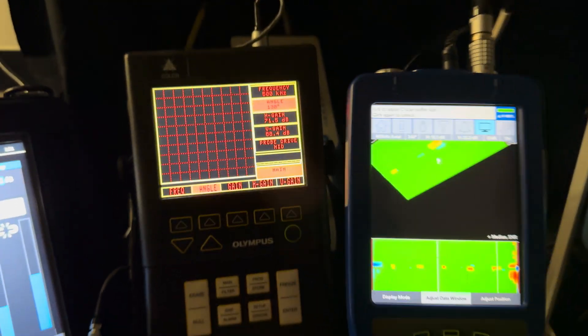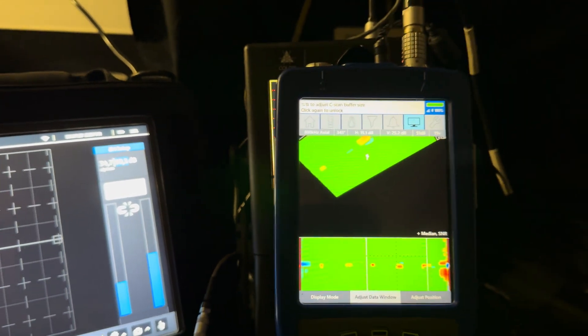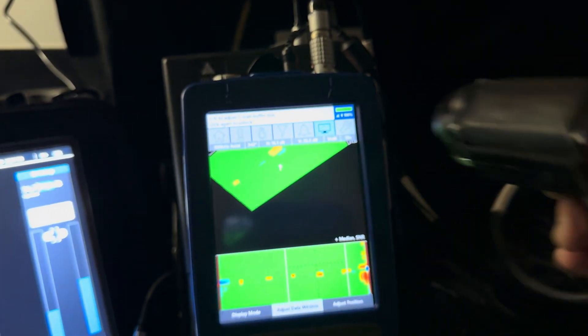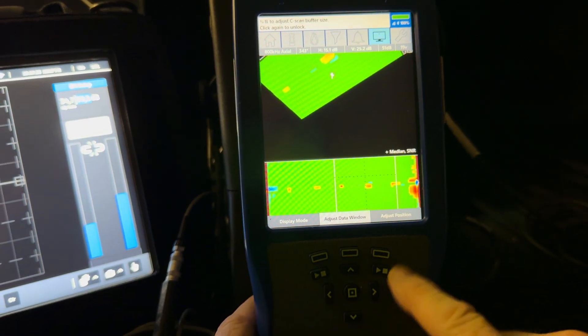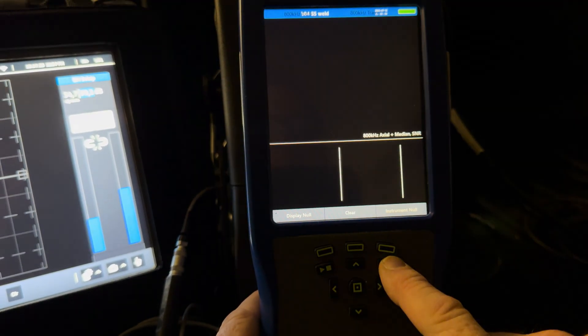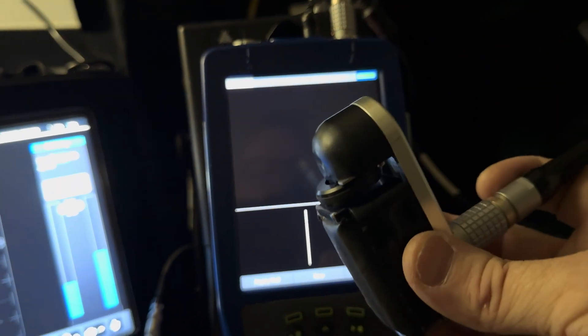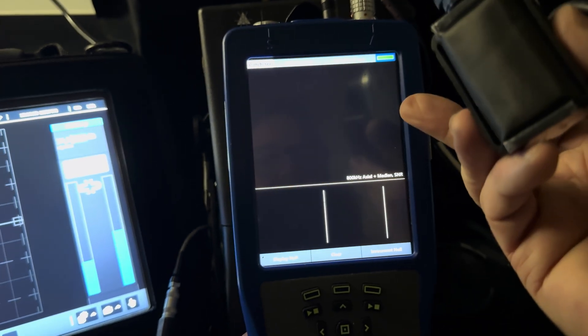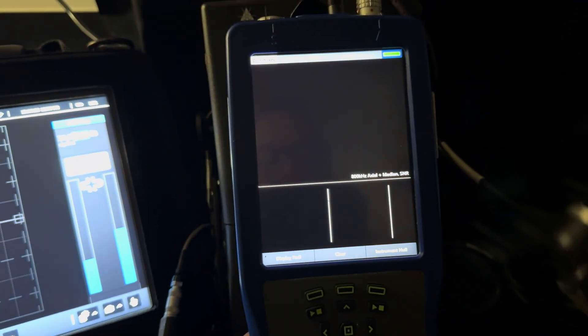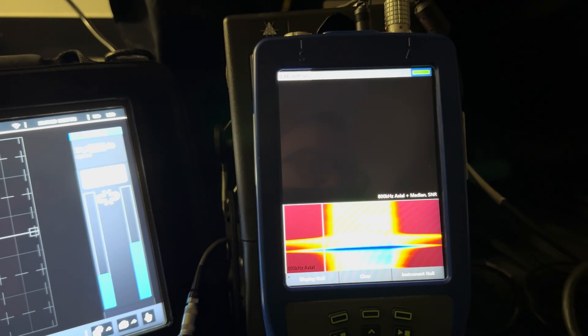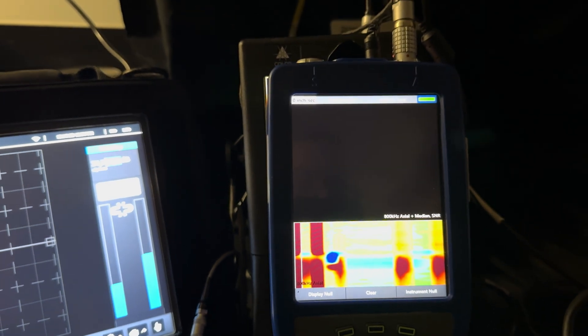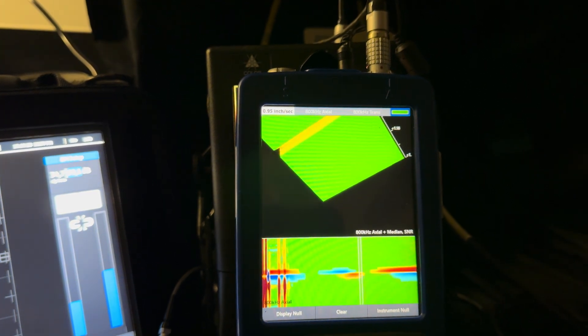Now the last tester I have to show you today, we're going to be using the MS-21C. Actually it's not the last, I still have a surprise for you. Okay, so this is a surface array probe and I'm going to just start up the tester, start the acquisition mode which is right there. And this array probe has an encoder wheel on it, so you're not going to see any data on your screen until this encoder wheel starts to move. But when I lay the array probe down onto the material and then pull the probe towards me, we're going to start seeing what we got there.